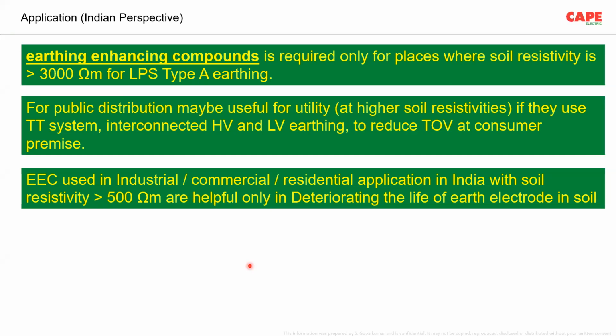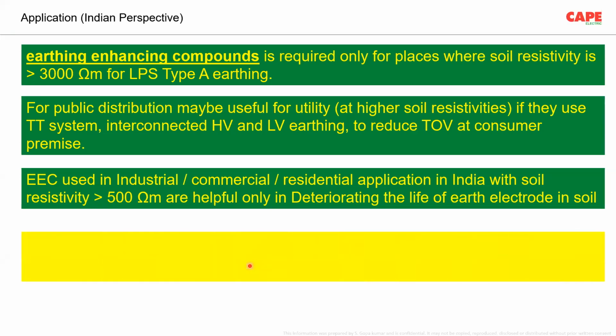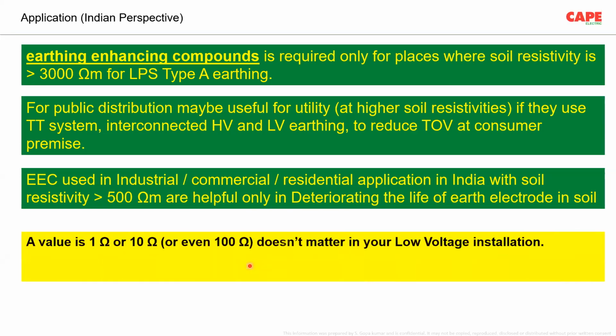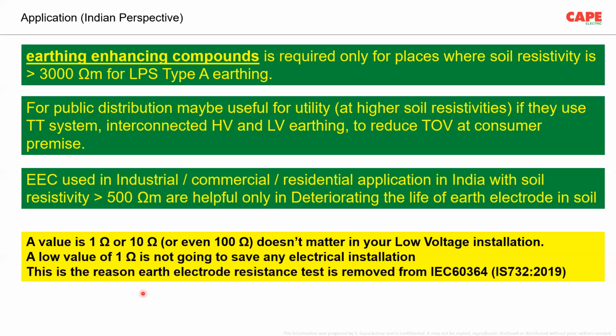I read it again. The earth enhancing compound used in India in places where the soil resistivity is greater than 500 ohm meter is helpful only in deteriorating the earth electrode in soil. It is never going to improve your system. A value of 10 ohm or 1 ohm or even 100 ohm doesn't matter in a low voltage electrical installation. A low value of 1 ohm is not going to save any electrical installation.